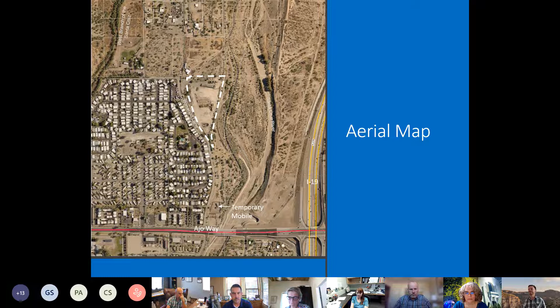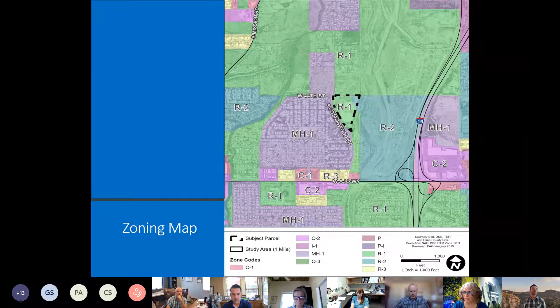TEP is requesting approval for an electric substation as a special exception land use in the residence zones R1 and R2 within the city of Tucson. There is adjacent mobile home zoning to the west, R1 to the north, and R2 to the east. TEP proposes building a new 138 kilovolt substation on a 10.7 acre site. The substation will connect to an existing transmission line adjacent to the property, and will convert energy from transmission level voltages to distribution levels for the safe delivery of electric service to area customers.